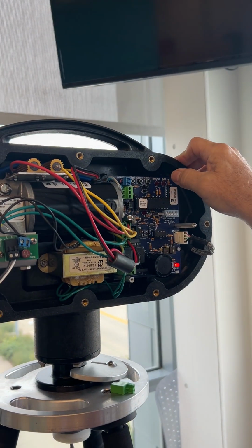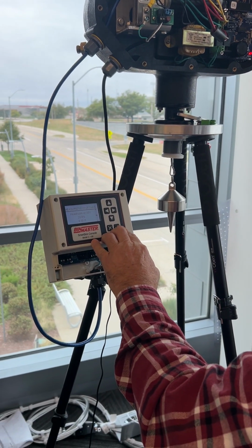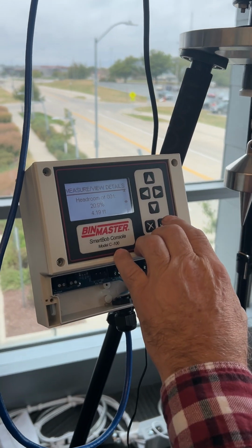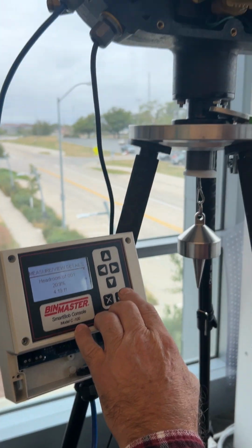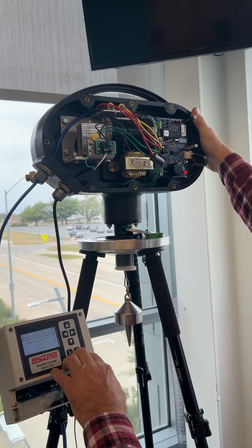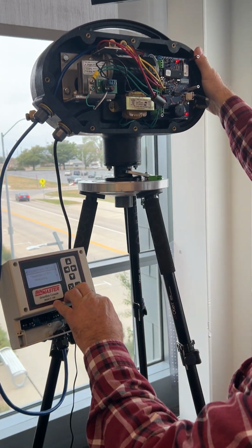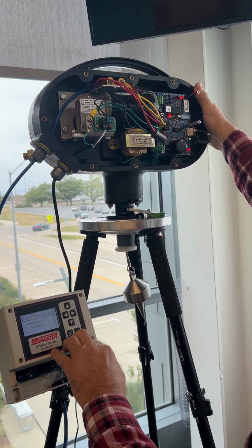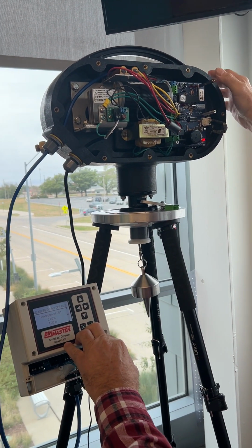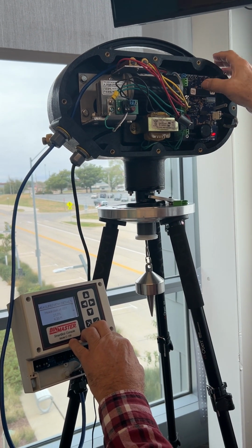the busy and the transmit, during a measurement request. So I'm going to request a measurement from our console here, and you should see the busy light flash and then the transmit light flash. So, and that should do it about every second during a measurement until it's done. If you don't see either of those flashing, then we're not getting to this processor.